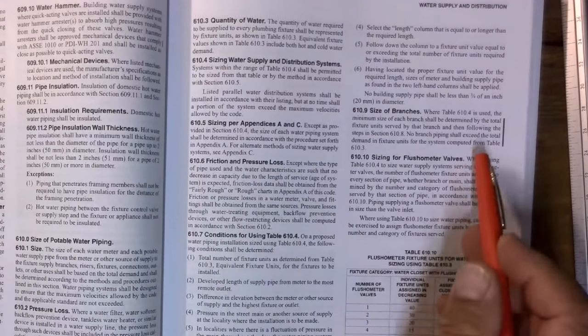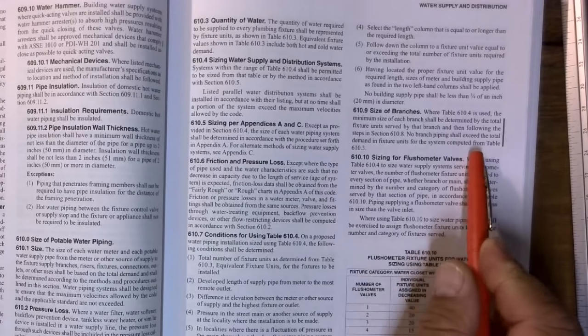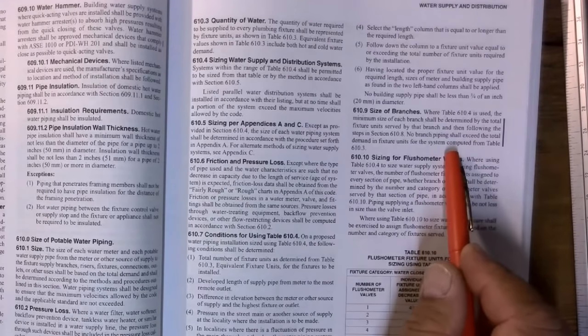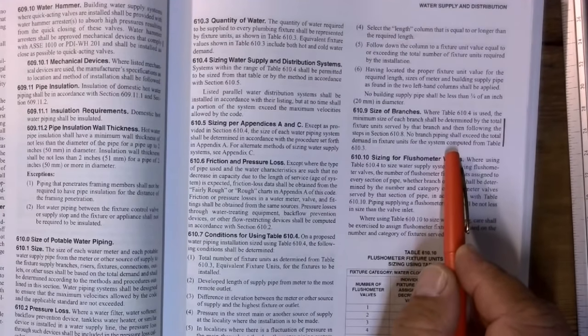The size of the branch. Where table 610.4 is used, the minimum size of each branch shall be determined by the total fixture units served by that branch. And then following the steps in 610.8, no branch piping shall exceed the total demand in fixture units for the system computed from table 610.3. This is a code change from the last code adopted.